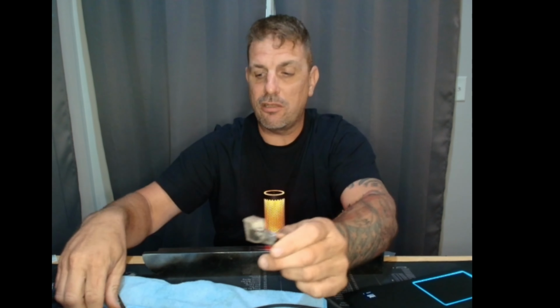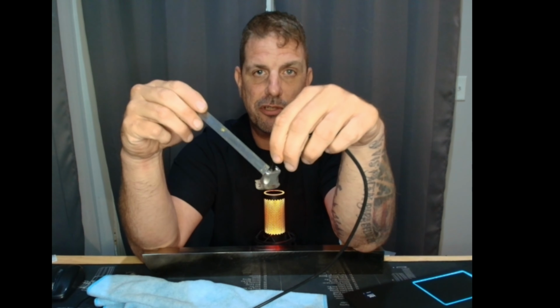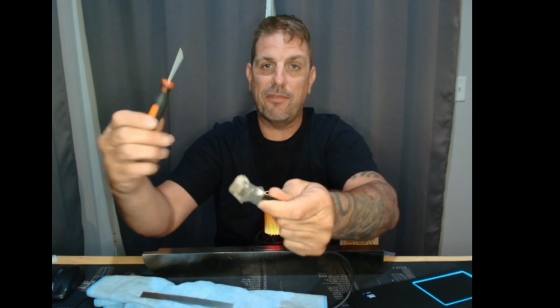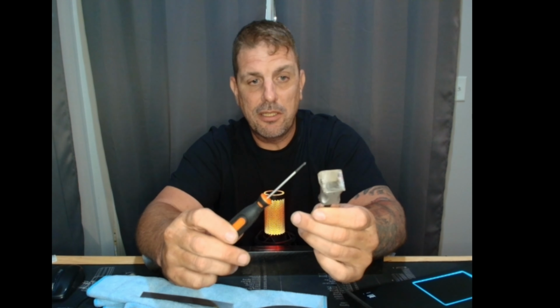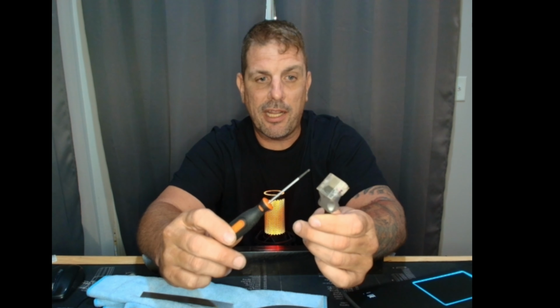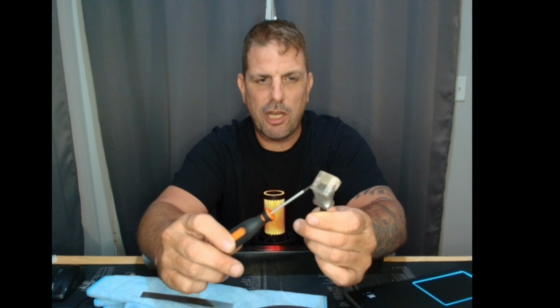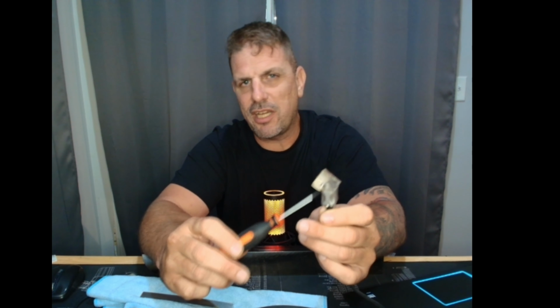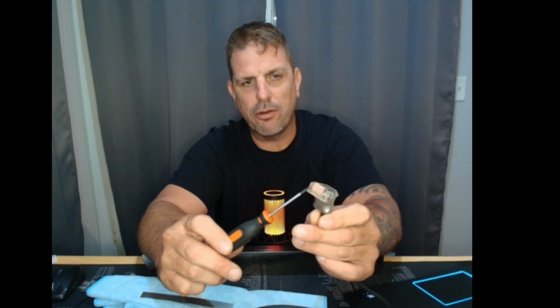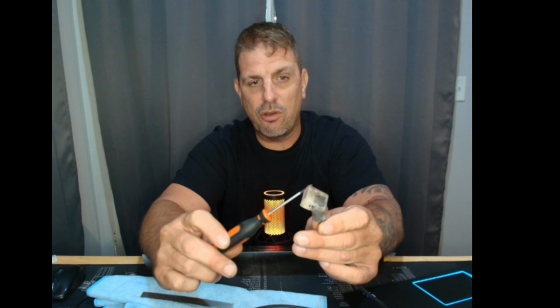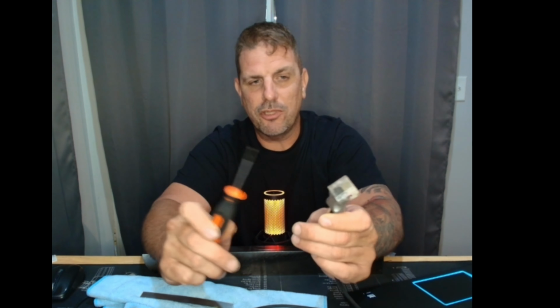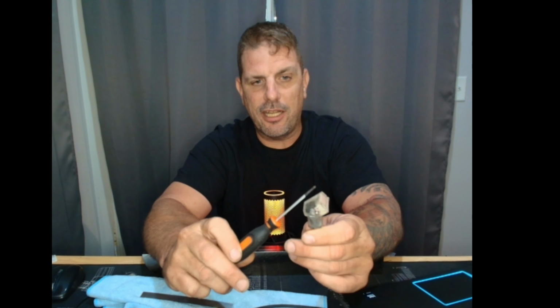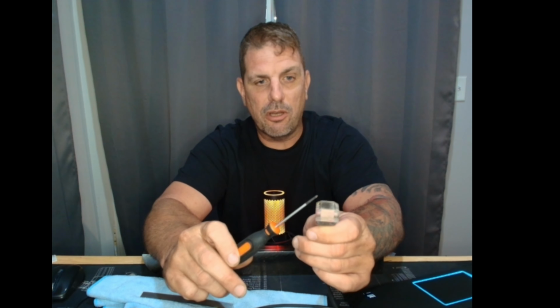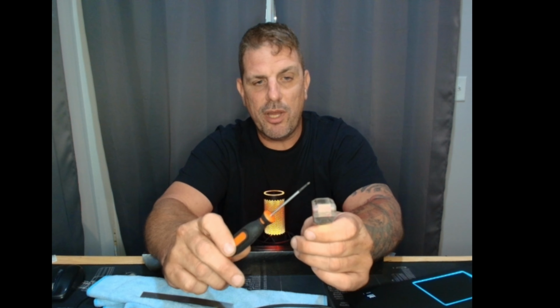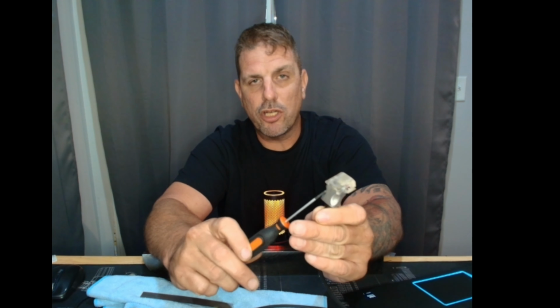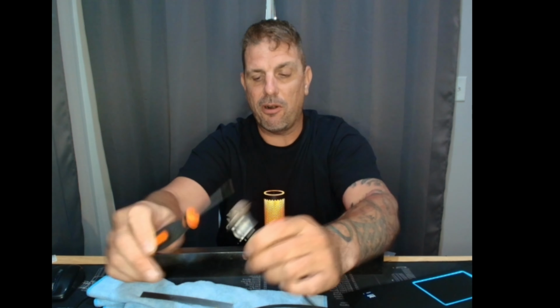Before we get started, unloosen these screws in the back, and you're going to need a Phillips screwdriver. Loosen them up, put some coupling in it, and make sure it's clean. Put some coupling in it, but don't tighten it up too much. If you tighten it up too much, they'll crack. It's real brittle at some points. If you really bear down on them, you'll break the wedge and crack it, and then it'll get all kinds of funky signals. So go ahead and recouple your wedge. Tighten it up. Remember, the 1 goes to the back, 16 goes to the front.